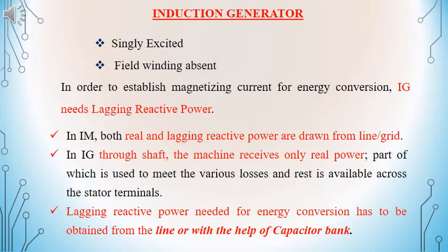When we consider induction generator, the real power is drawn from the shaft. That is the mechanical input given through the shaft to the machine. It will be meeting the various losses in the system and the rest of the mechanical power input will be converted to electrical power. For energy conversion, in order to have the lagging power, it should be either drawn from the line or from the supply side or from the bus, or it should be provided by using a capacitor bank.